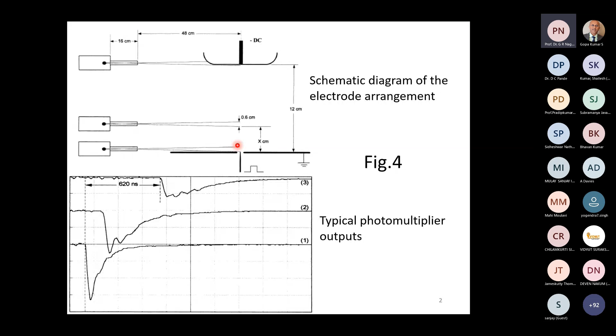And then the important point is this experiment at the given spacing and at a given voltage level is repeated 20 times. It's a very important point for us to note. So statistical behavior is completely studied. It's not avoided. So at each position, for a given voltage here, the pulse is given and we see whether the streamer has propagated for that particular distance. For example, it may be 2 centimeters. Apply a certain voltage there. For example, stress being equal to 450 kV per meter or whatever it is, and then apply 20 pulses and see how many times it has propagated to that distance or not. It's a very, very beautifully designed experiment. Now we'll see the results presently. We'll see that it's really exciting to see how things go.